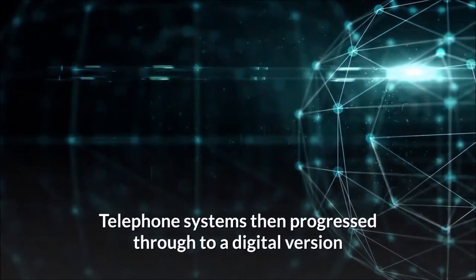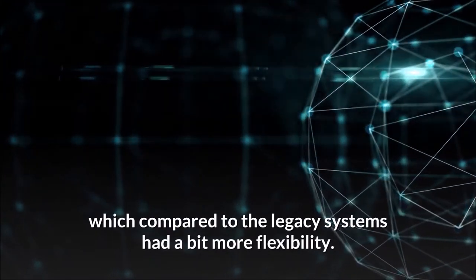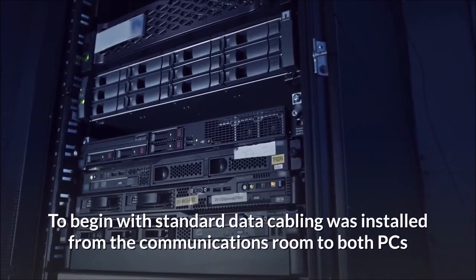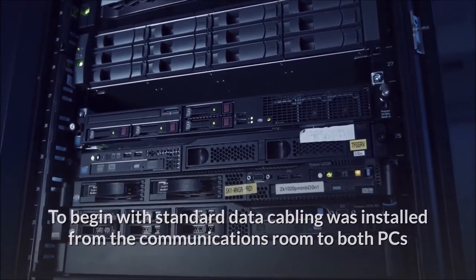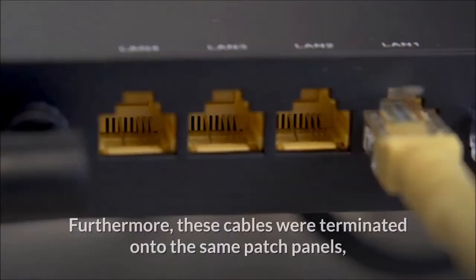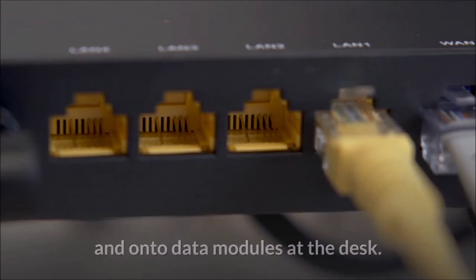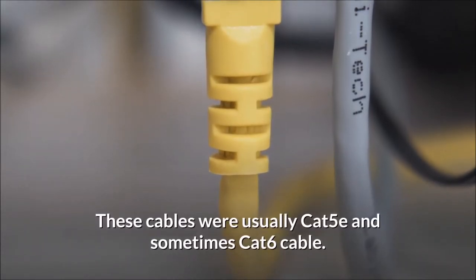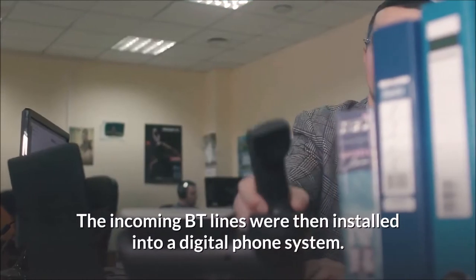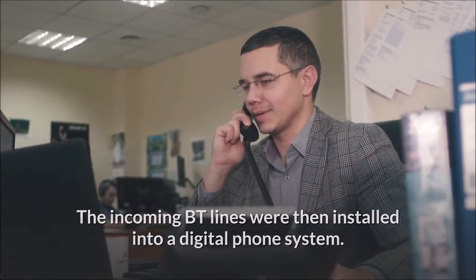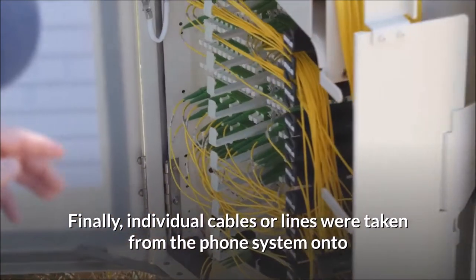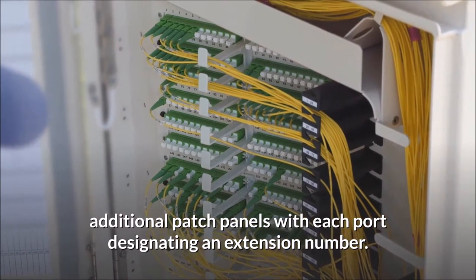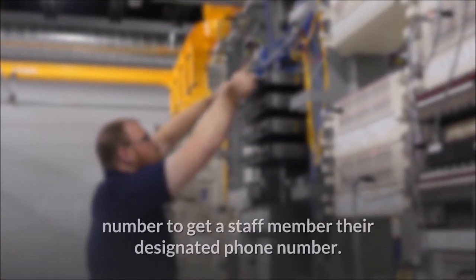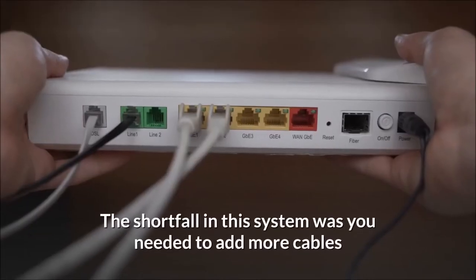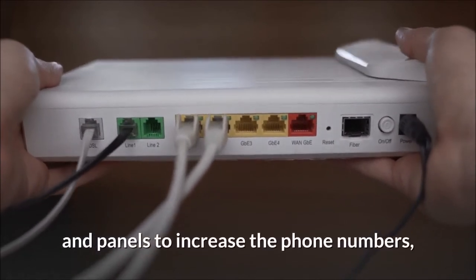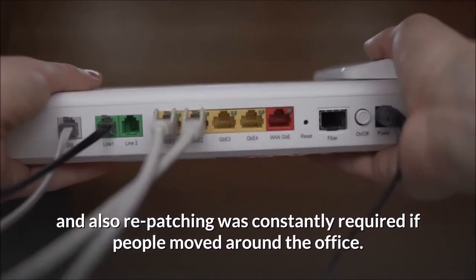Therefore you would have two separate installations. Digital systems: telephone systems then progressed through to a digital version which, compared to legacy systems, had a bit more flexibility. To begin with, standard data cabling was installed from the communications room to both PCs and telephones using separate data cables. These cables were terminated onto the same patch panels and onto data modules at the desk, usually Cat5e and sometimes Cat6. The incoming BT lines were then installed into a digital phone system. Individual cables or lines were taken from the phone system onto additional patch panels, with each port designating an extension number. These ports would then be patched to an outlet to get a staff member their designated phone number. The shortfall in this system was that you needed to add more cables and panels to increase the phone numbers, and repatching was constantly required if people moved around the office.